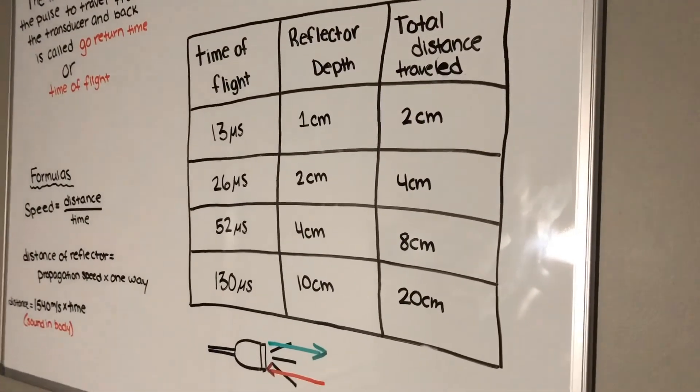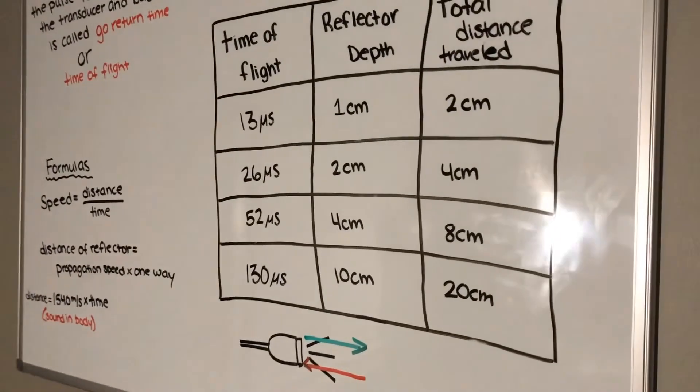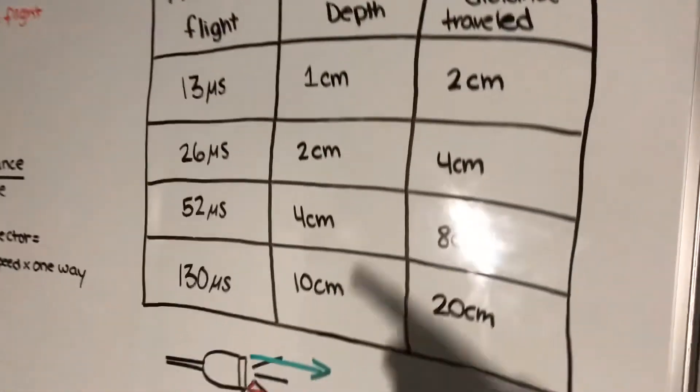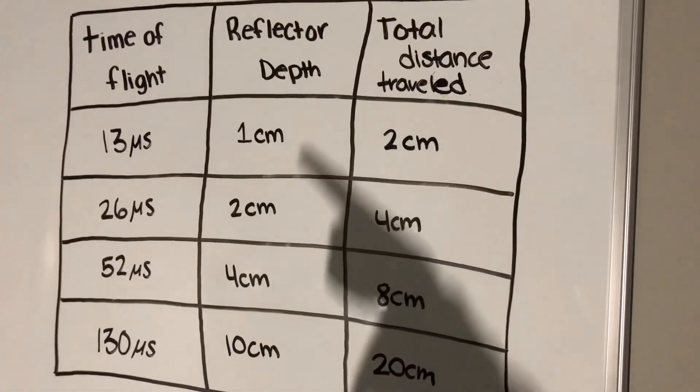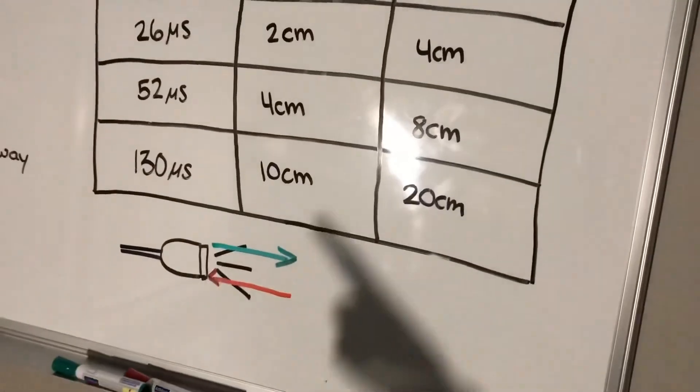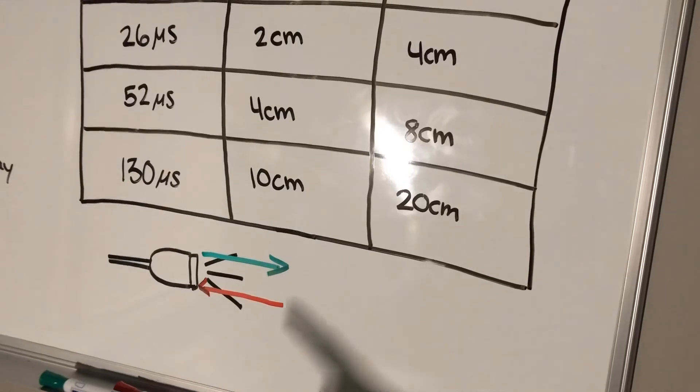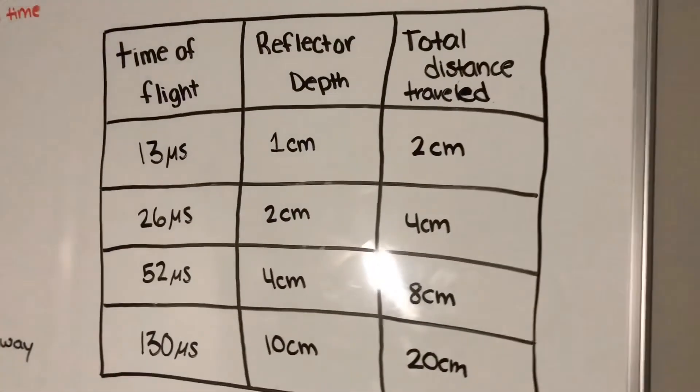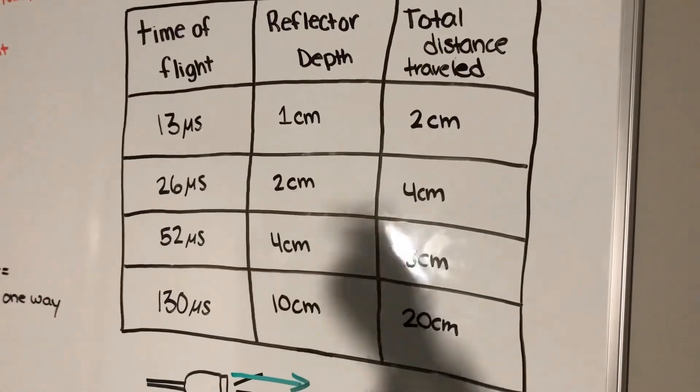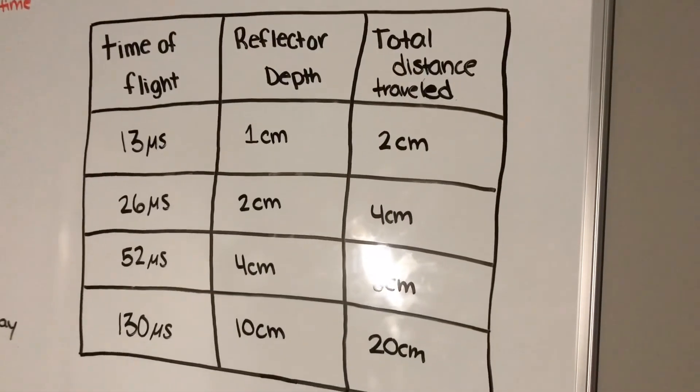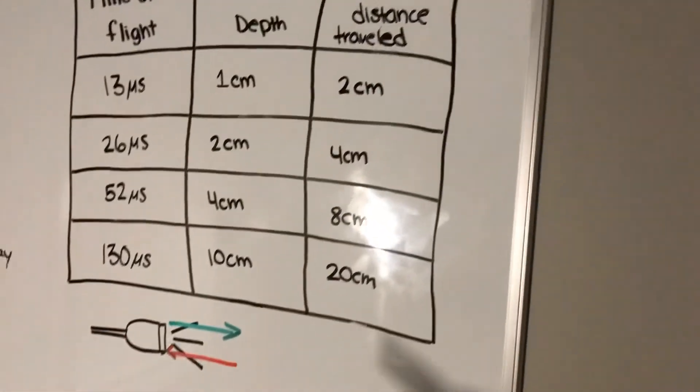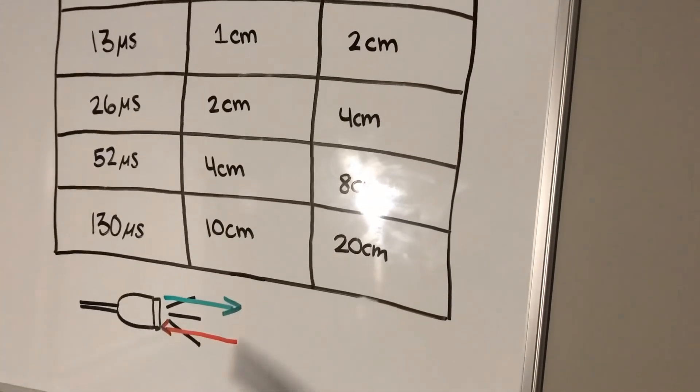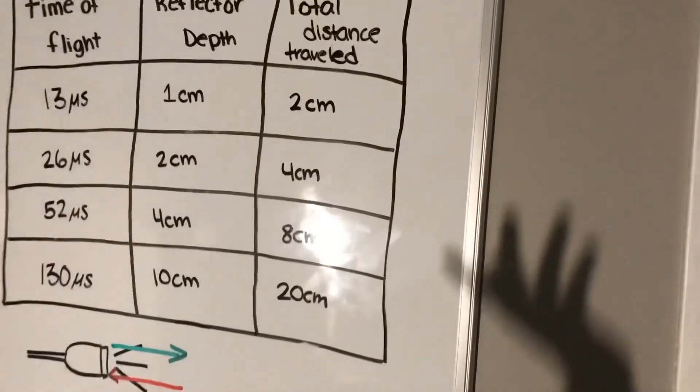Here we have the 13 microsecond rule, which is the time of flight. So when the reflector is going towards the body, it's one centimeter, and the total distance would be two because it's coming out one, going in one. Then if the time of flight is 26 microseconds, then the reflector depth would be two centimeters, which means the total distance traveled, if it's two centimeters out, two centimeters back, it would be four centimeters.